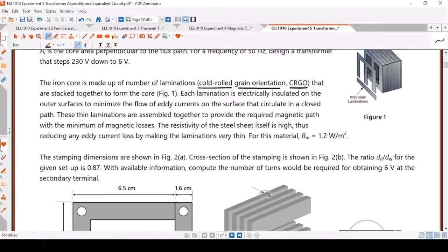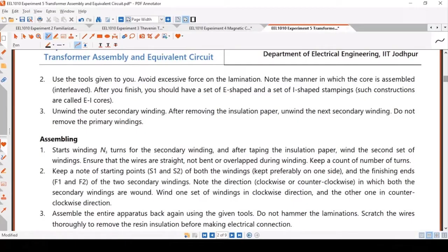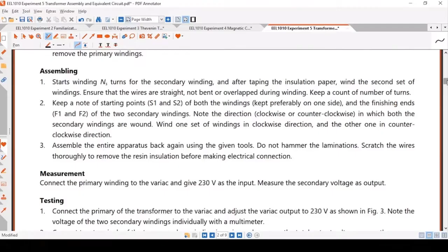We opened the clampings, removed the screws, removed the core, then unwound the secondary winding. There were two secondary windings in this transformer. We removed the paper, then removed the secondary winding, but did not touch the primary winding. We straightened out those turns, then wound them back making sure there was no air gap. The next step was to measure the flux.